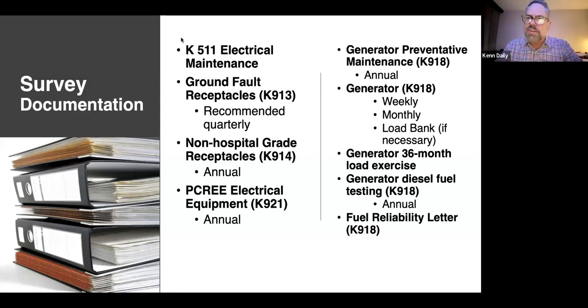And then with the addition of the code, we added non-hospital grade receptacles. Again, you test that once a year. You're testing integrity, polarity, neutral, and the retention force, the ability to pull that device out. And that's supposed to be no less than 4 ounces.